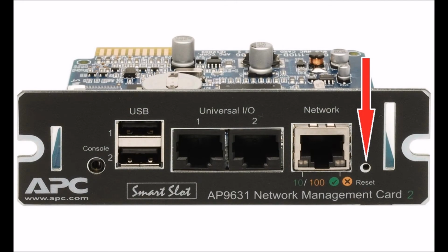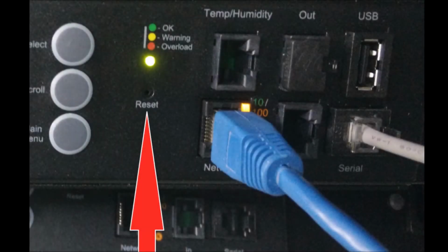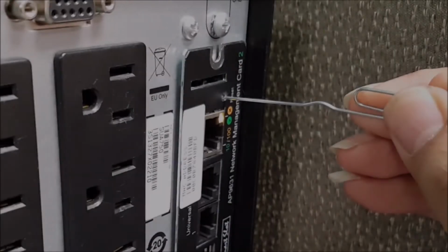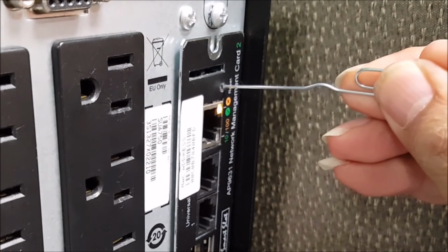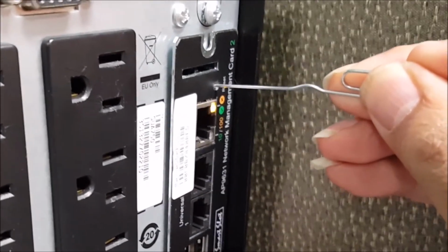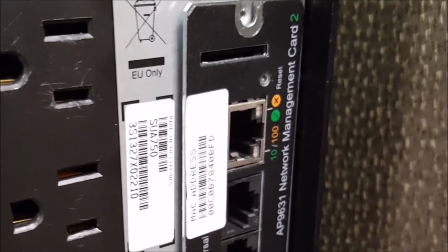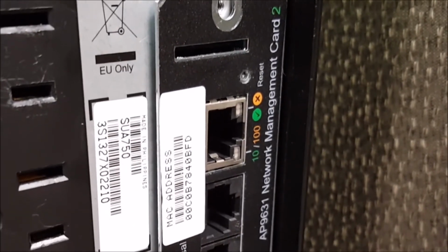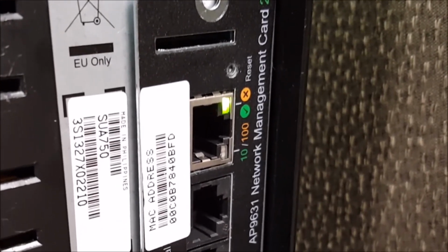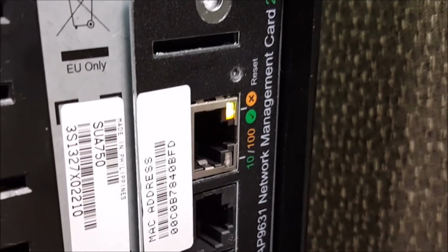Once the terminal emulation software is properly configured, you'll next need to press the reset button on your network management card or Rack PDU. To press the reset button, all you will need is a paperclip or similar tool to press the reset button on the card or PDU. If done properly, you will then see the LED lights flashing alternating between amber and green. Once you've done that, you know that the card is properly rebooting.